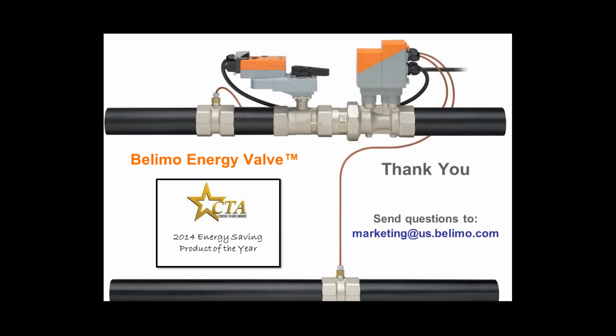Just as an example, let's say it's evening time and you're going to go into a heavy economizer mode, bringing in tons of cool air from the outside. Well, it's really hard to hit delta T set points if you're blowing cool air across your chilled water coils. So in a lot of cases, people will write a routine that says disable delta T management when we go into economizing mode, above X% open on your outside air damper or something along those lines. But yes, we can control all of those things.